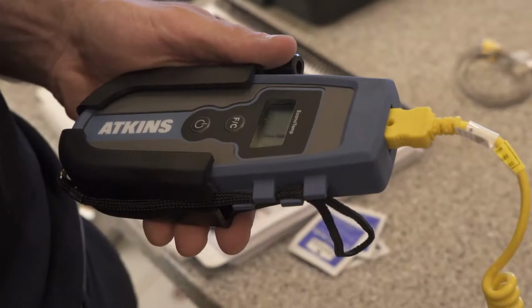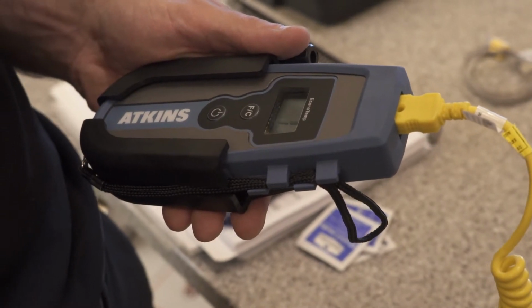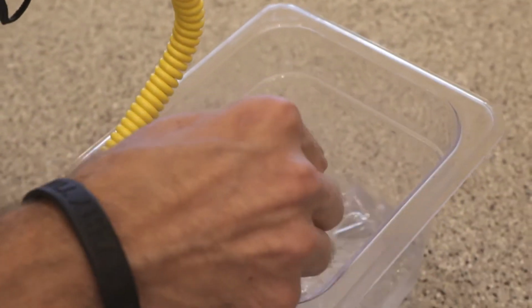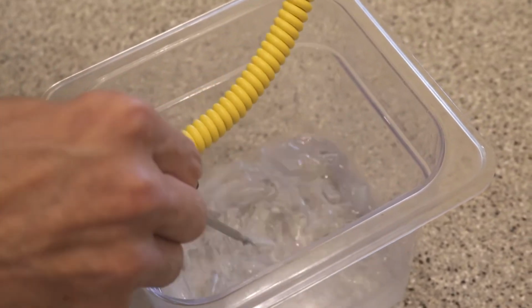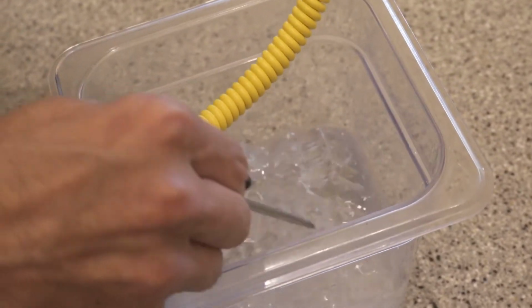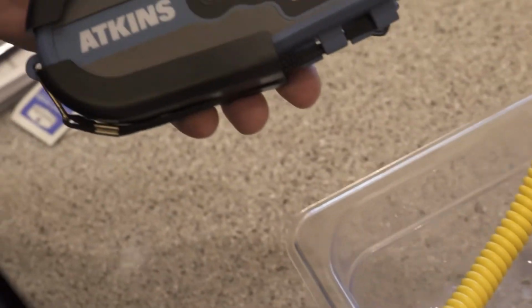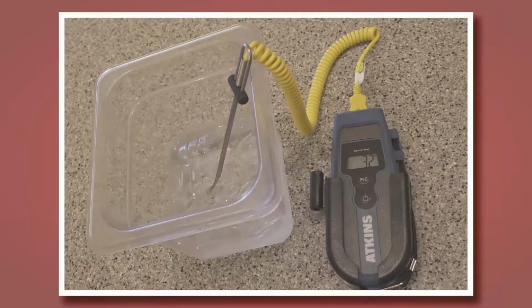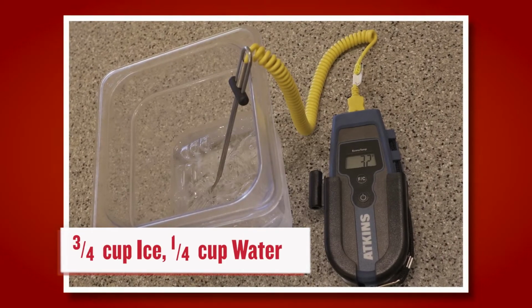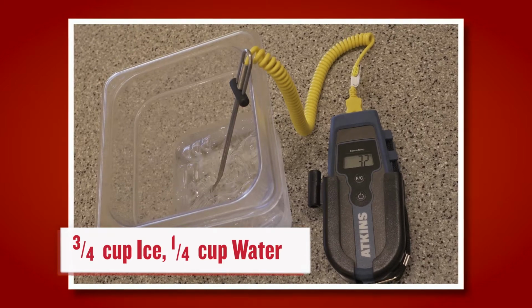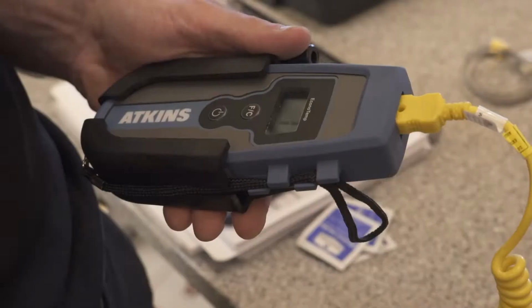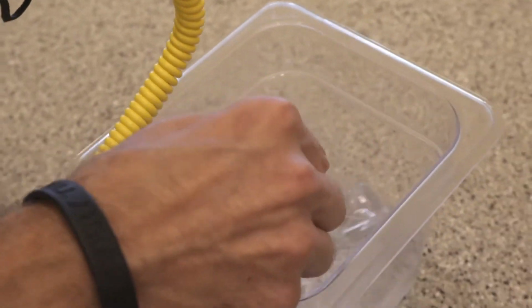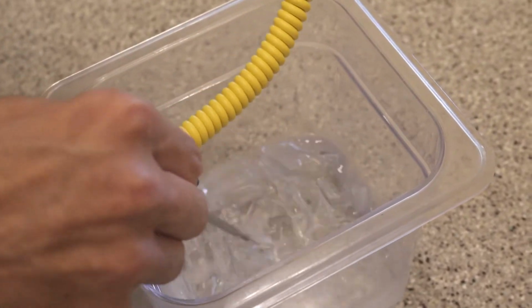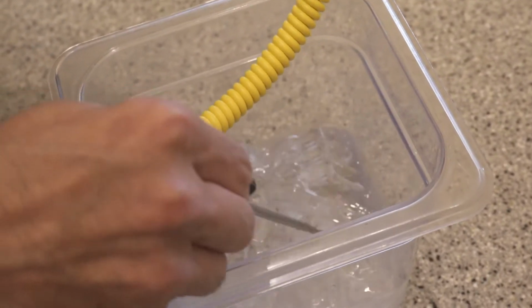It is recommended you verify your thermometer is calibrated once a week. A best practice is to check the calibration on the same day weekly. The method for checking calibration is the ice bath method. A proper ice bath includes a combination of 3/4 cup of crushed ice to 1/4 cup of water. Ice water made with large ice cubes will usually not reach 32 degrees unless vigorously and constantly stirred.